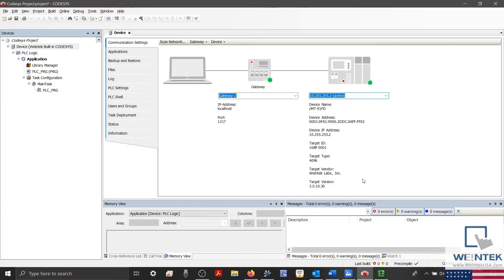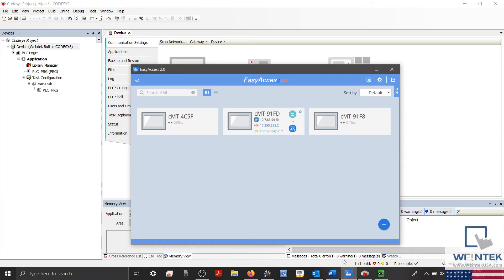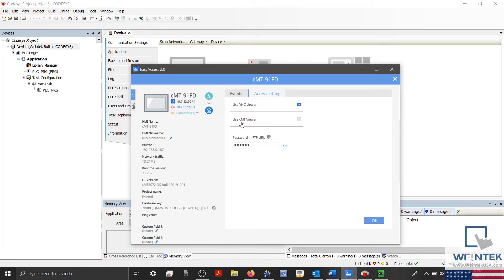Earlier, I also mentioned that I would discuss our Codesys login feature. When enabled, it will allow us to connect to our Codesys application through LAN-2 on our HMI. What this means is that within the Codesys IDE, we can enter the LAN-2 IP to connect to our built-in Codesys application.